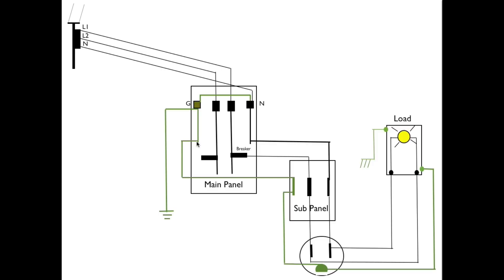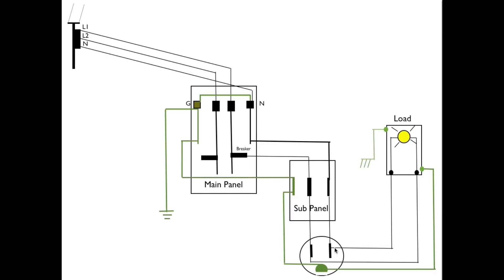The problem with this is let's say I had a loose wire on the ground. Let's say I eliminated this neutral line right here and just use the ground. I could hook the ground right to here. If I did that it'd be a current carrying wire. If for some reason that ground wire was broken no longer had continuity then I would have no chassis ground on this load and the load would be hot.